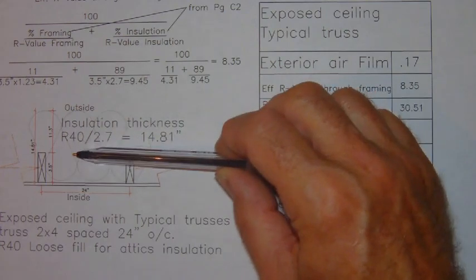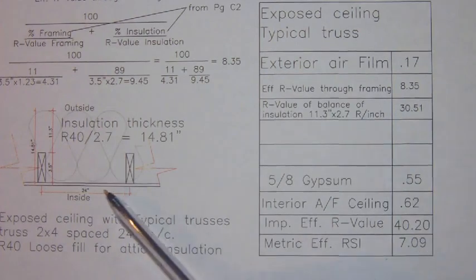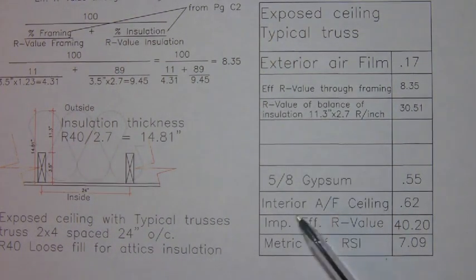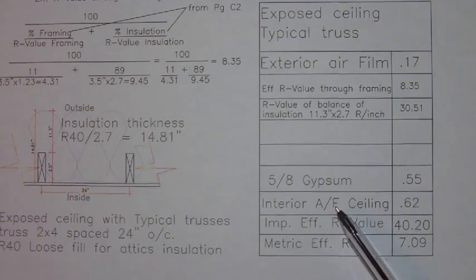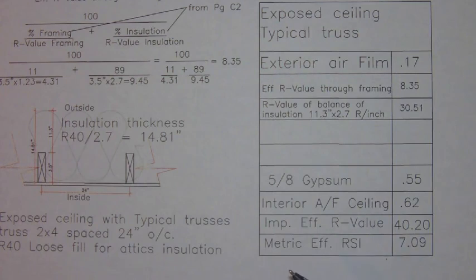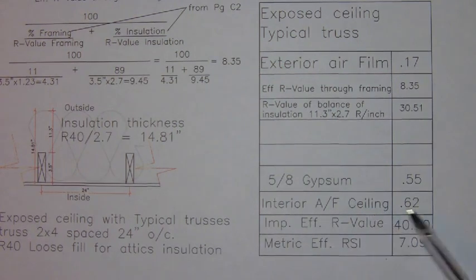So that's going to be this 11.3 inches of insulation. Then we've got our 5/8 layer of gypsum. So gypsum is listed at 0.88 per inch. So 5/8 is 0.625, so 0.625 times 0.88 gives us 0.55. The interior air film for an exposed ceiling has an R-value of 0.62.